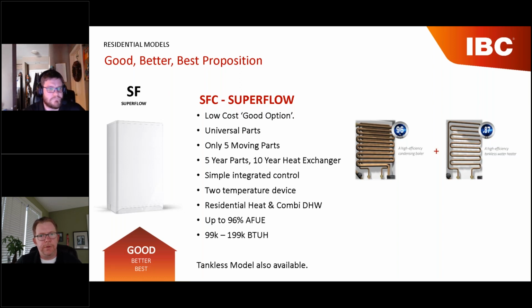Now, what's truly unique about this unit is the heat exchanger design. IBC's heat exchanger is truly unique in that you'd have to think long and hard to ever see one fail. Chris, I'll tell you the story. We had somebody make a mistake, and I'm not going to get into it, but it had nothing to do with the boiler, and the heat exchanger failed. I tried to get a replacement heat exchanger, and it turns out there's no part in the system, not just in North America, but even in Europe. I was like, what do you mean you killed the heat exchanger? It had nothing to do with water quality, nothing to do with the boiler. It was quite a rigmarole, because the design of this heat exchanger is such that it's not going to foul and fail because of the single pass design.